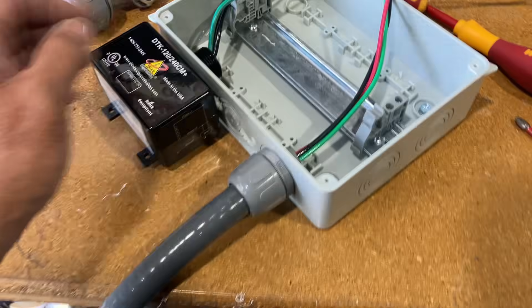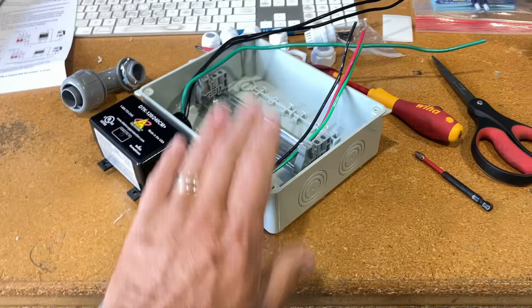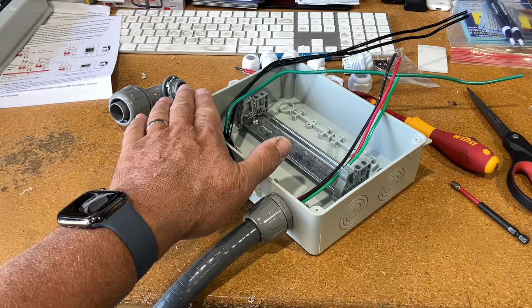So one of the things I like to do is drill a hole through one of the corners and secure the box to my workbench, aka my office desk, and that allows me to keep it in place while I'm trying to maneuver everything in here. I just ran a 1/2-inch liquid tight with 3 conductors, black, red, and ground. This is the load side of the disconnect surge protection device. This is going to that outdoor unit, so my ACIQ, for example. This is going to be attached to my incoming mains or incoming power, L1, L2. And then we'll finagle those 2 devices in here as well.